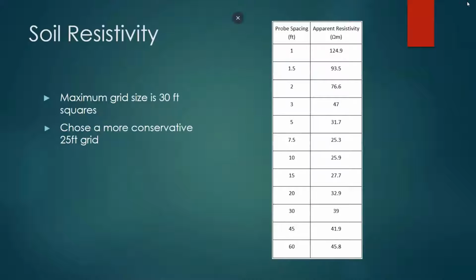So using this soil resistivity chart, it was determined that the maximum grid size would be 30-foot squares. However, we chose a more conservative 25-foot square grid. This allows us more flexibility in moving the grounding grid, either shifting it left and right around foundations. Along with that, it gives us more safety in the substation.